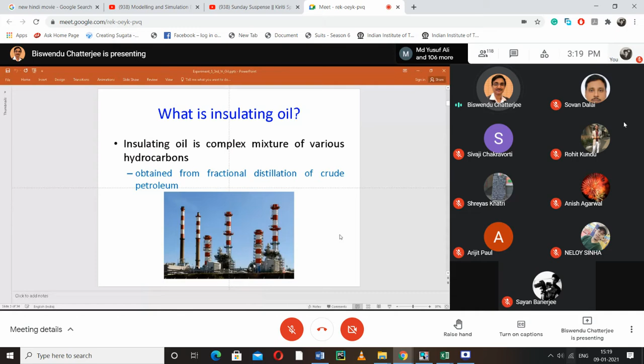So what are the uses of insulating oil? The main use is in oil filled transformers. Sir has demonstrated there are huge transformers in the order of 500 MVA, 1000 MVA, that are filled with oil, and that oil is the insulating oil. What oil serves? Not only insulation, but since it is a liquid, circulating current can flow, and this oil can be used for heat dissipation purposes.